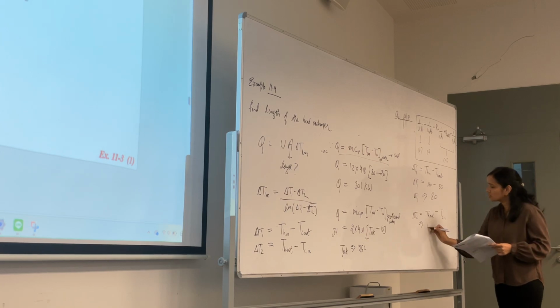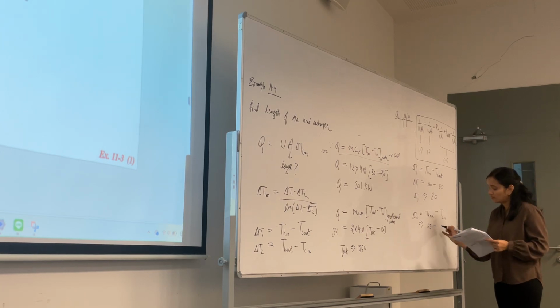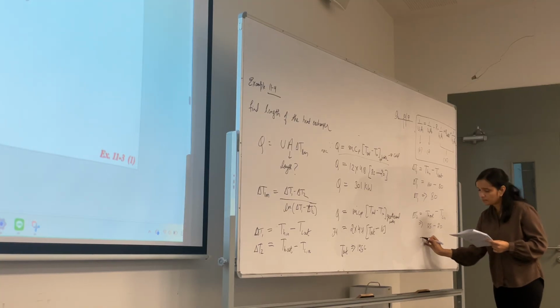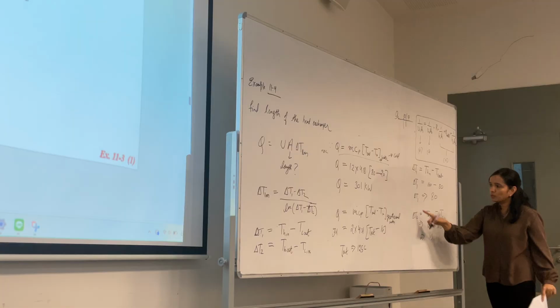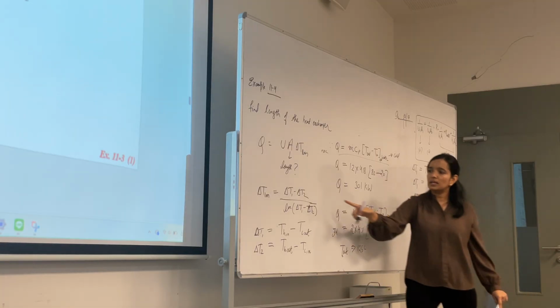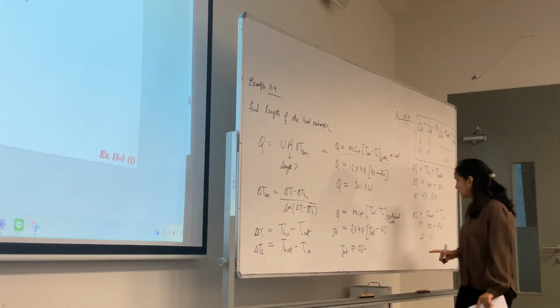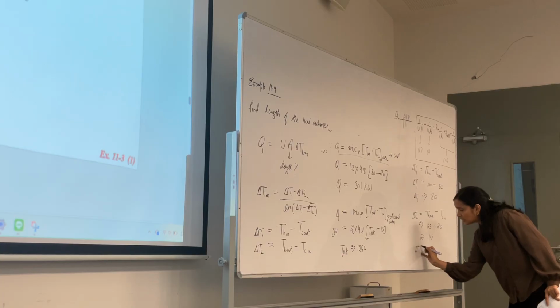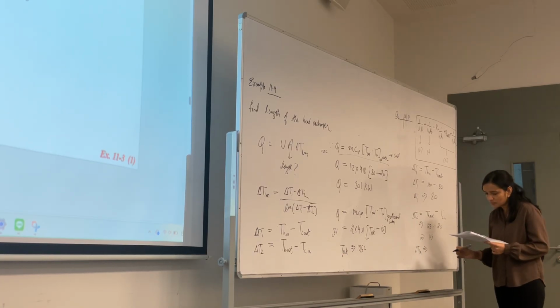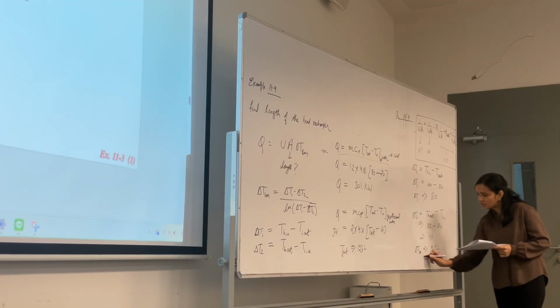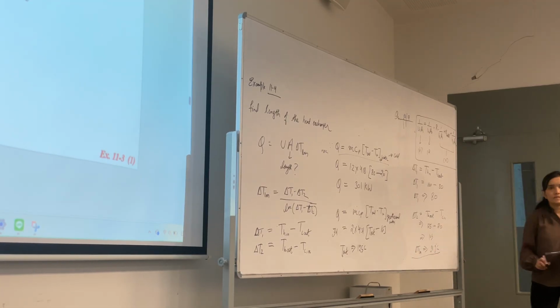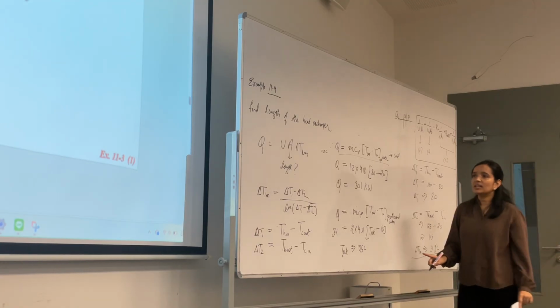Hot out we have just calculated, 125 minus 20, so get 105. Input this value in here. Then you get delta TLM. So I will directly write delta TLM will be 91.9 degrees Celsius. Okay. Now you have delta TLM.